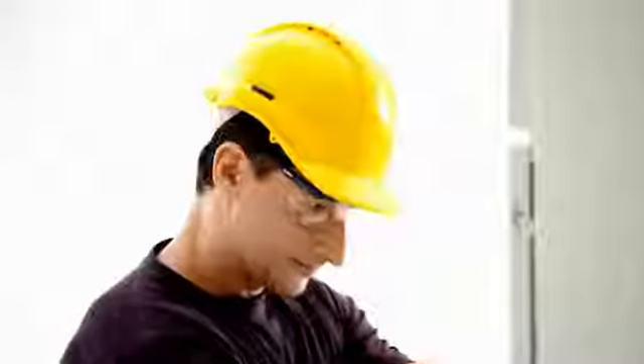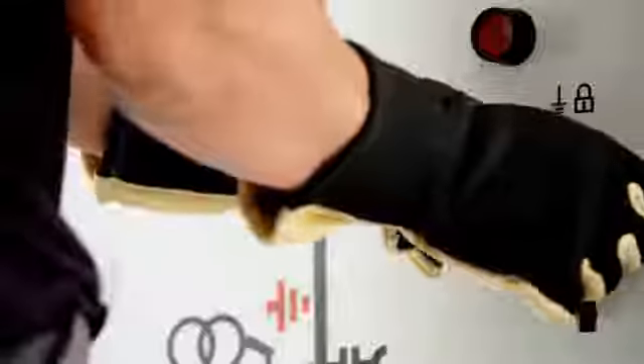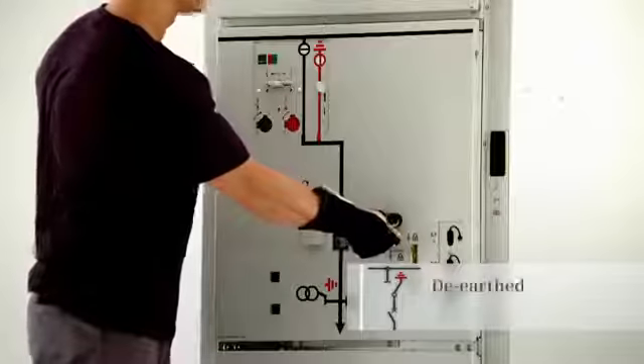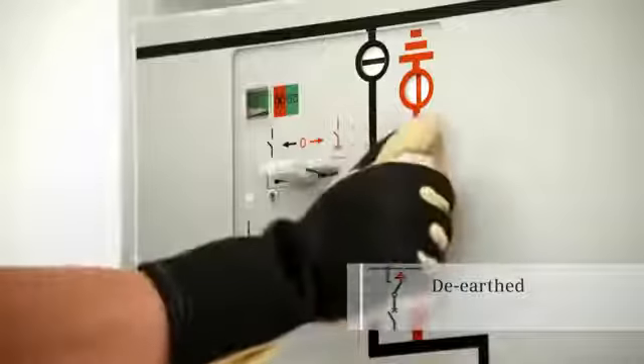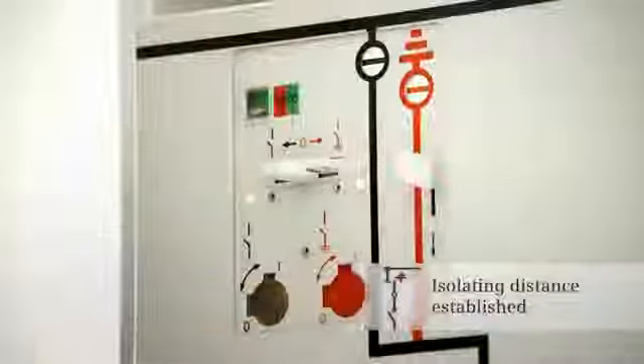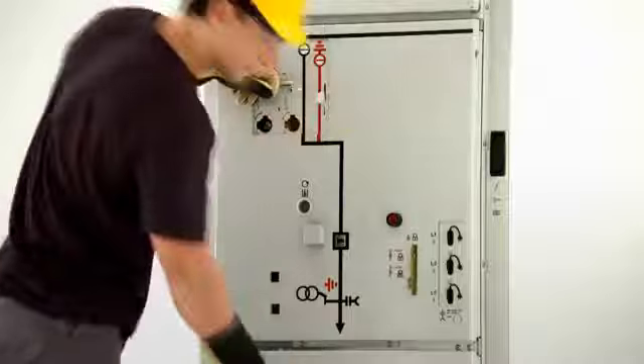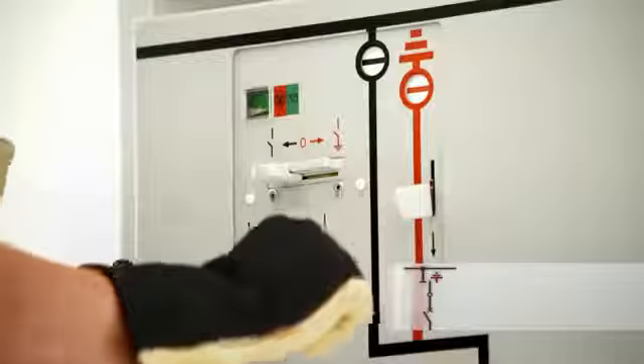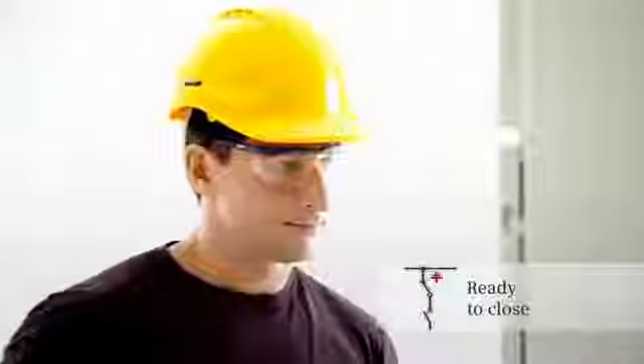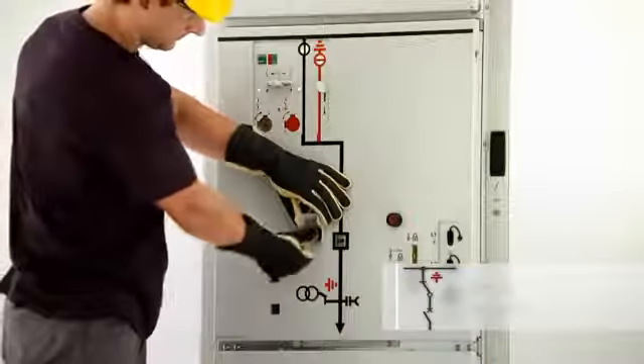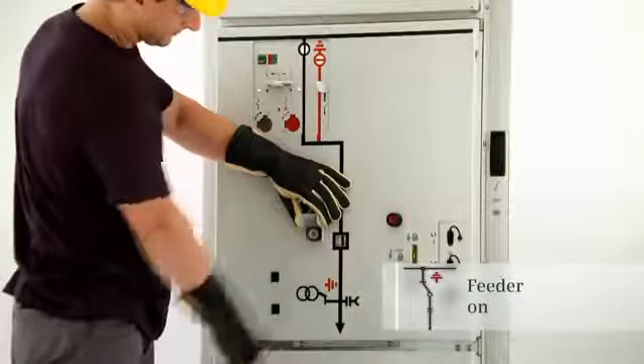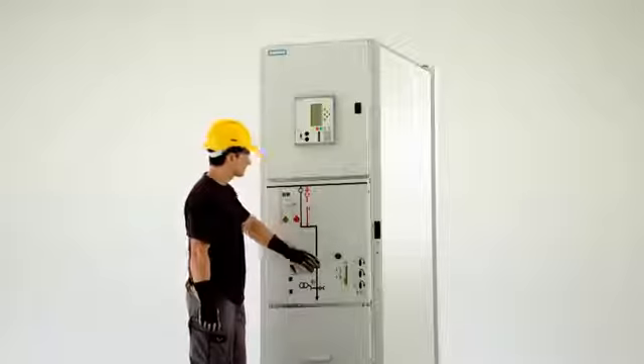To de-earth this feeder, the padlock must first be removed, rendering the locking device inoperative. The circuit breaker can then be switched to the open position and hence the feeder can be de-earthed. The three-position disconnector can then be switched from the ready-to-earth position to the open position and then to the closed position. The feeder is re-energized by closing the circuit breaker. The choose and execute principle. So, switching is both reliable and safe.